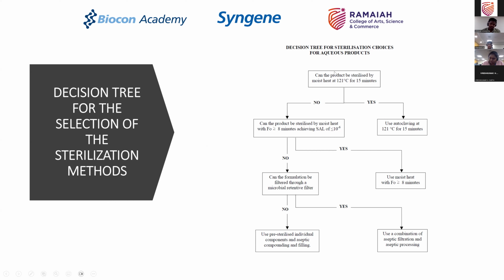So if I were to rewrite this statement again from a tree perspective, because this is something which is defined by CPMP that we all follow. So 121 degrees centigrade for 15 minutes is using absolute saturated steam under zero air condition. Now there may be situations where you don't have 100% saturated steam, and in that situation the time may be slightly higher, so you could apply that.